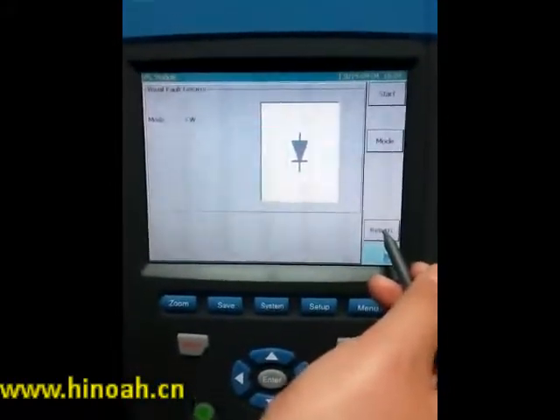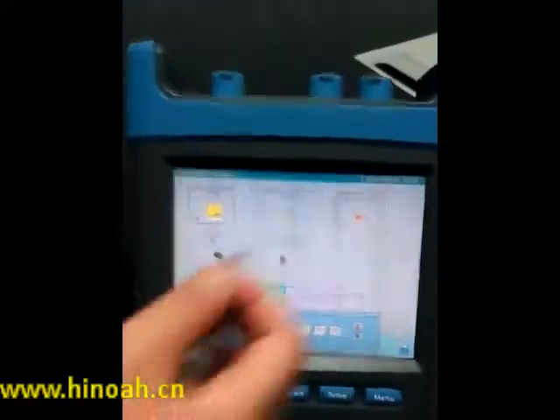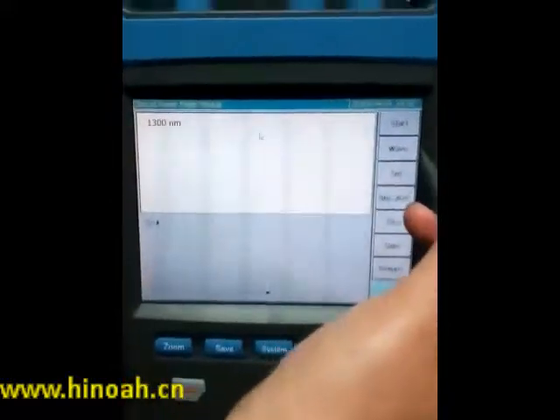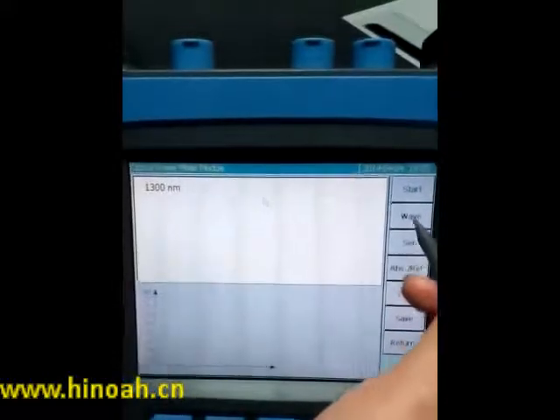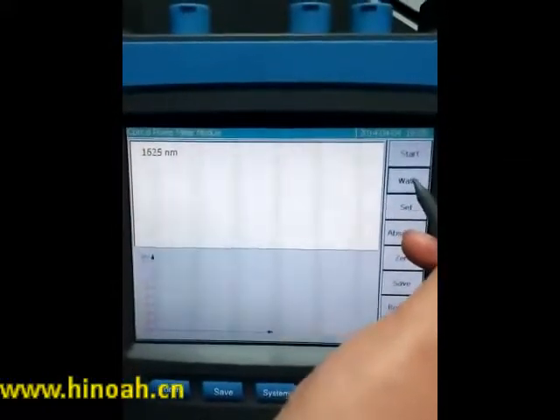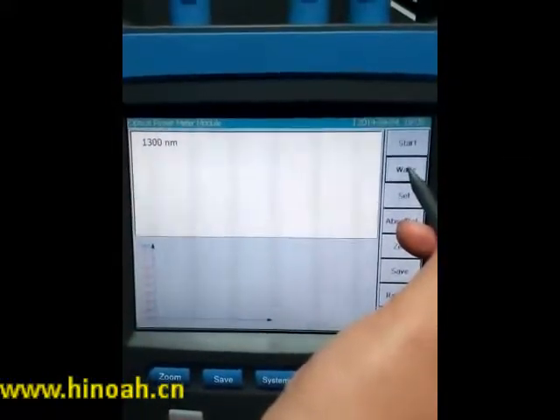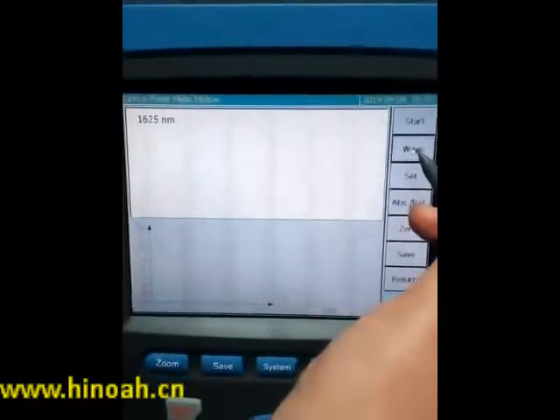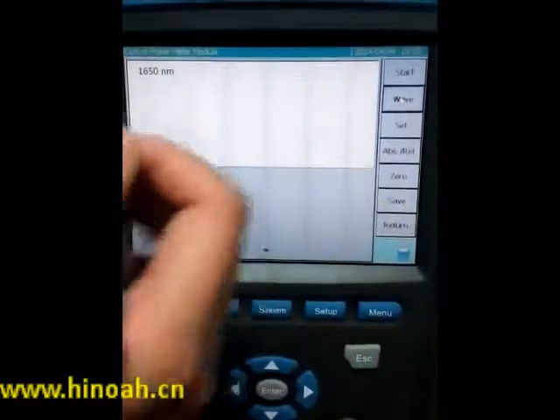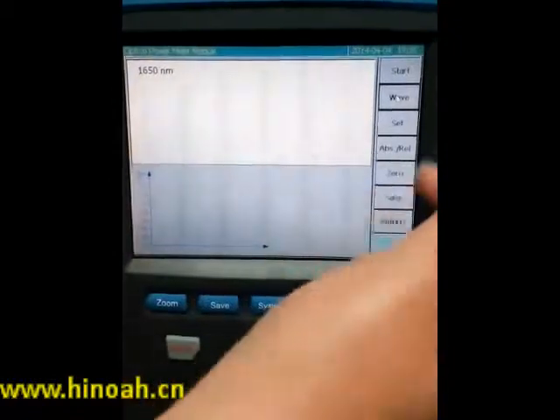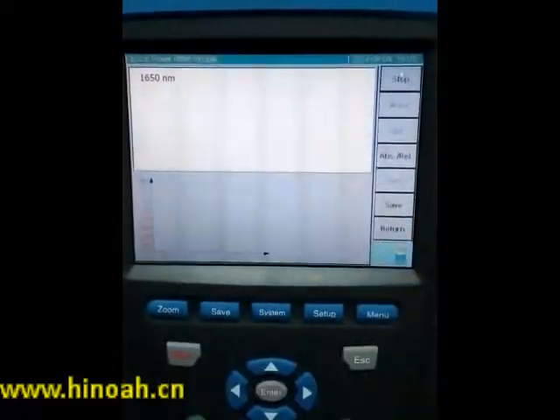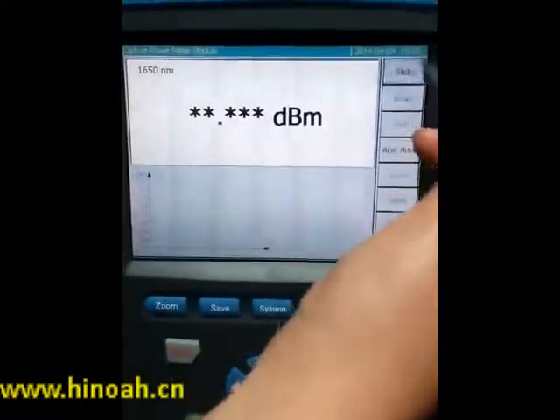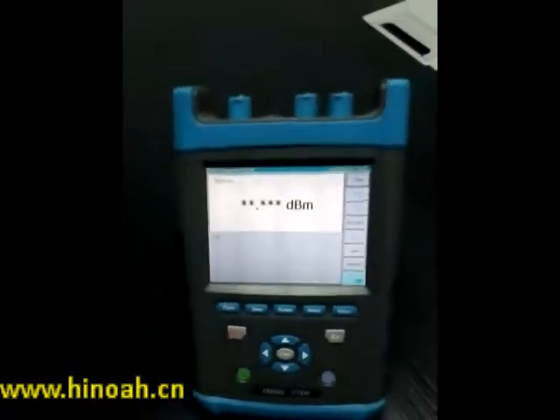If we want to use the optical parameter function, press Return to go back to the main interface, then press Optical Parameter. Here it has seven wavelength options. Press Wave and you can choose the option you want — it ranges from 850 nm to 1650 nm. Press Start to begin, and press Stop when you want it to stop. This is the optical parameter function.